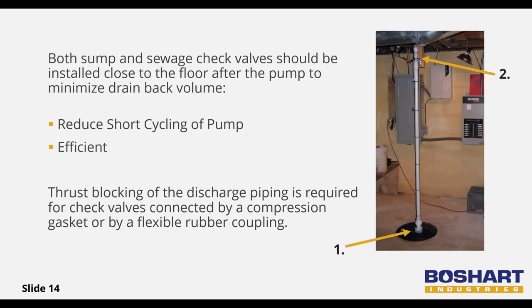Sump pump check valves should be installed close to the floor after the pump (arrow one). This reduces the amount of water that drains back to the pump after each cycle. The closer the check valve is to the pump, the less the pump has to re-eject water that drains back down to the pit, making the system more efficient and prolonging pump life.